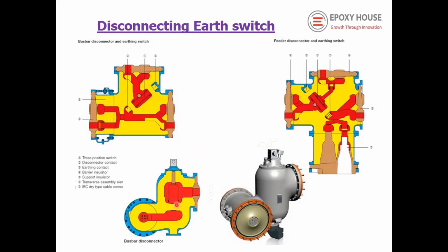But here, most of the bays have the earth switch, and they also use a high speed earth switch because of the charged energy, where charged cable systems are connected. In that case, a lot of high frequency transients are possible.